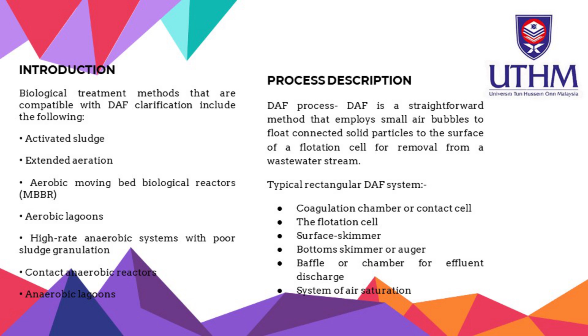For the process description, DAF is well known as a straightforward method that employs small air bubbles to float and then collect solid particles at the surface of a flotation cell for removal from a wastewater stream. A typical rectangular DAF system consists of, for example, a coagulation chamber, the flotation cell, a surface skimmer, a bottom skimmer, a baffle or chamber for effluent discharge, and lastly, a system of air saturation.